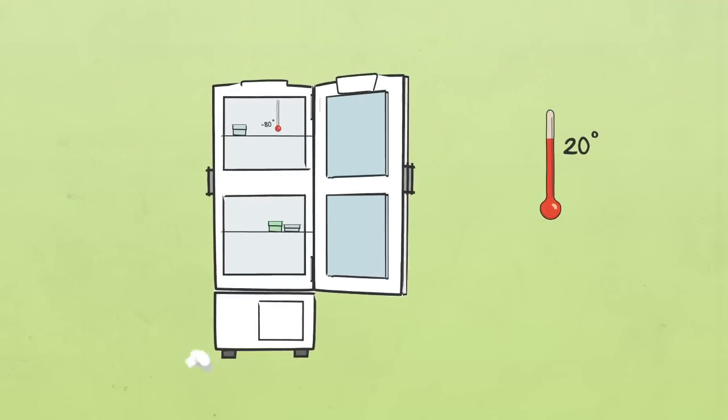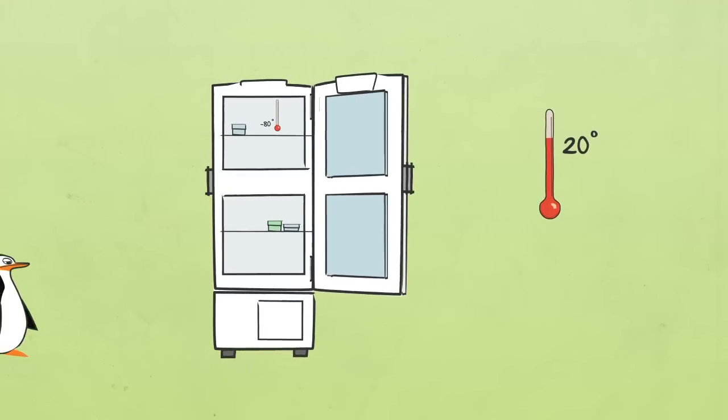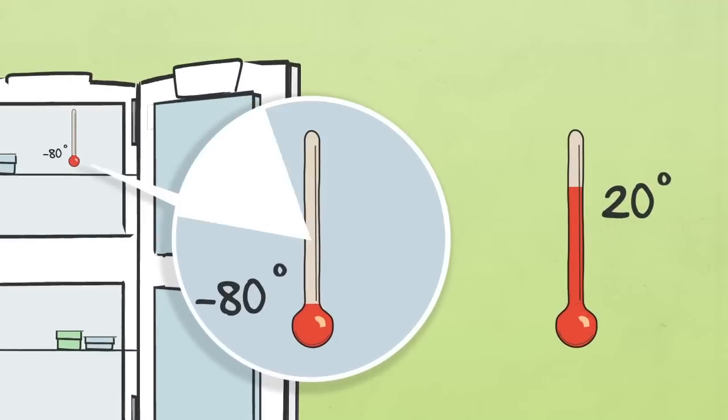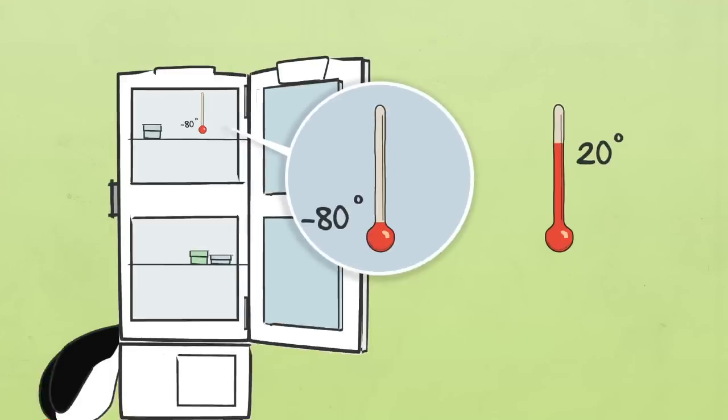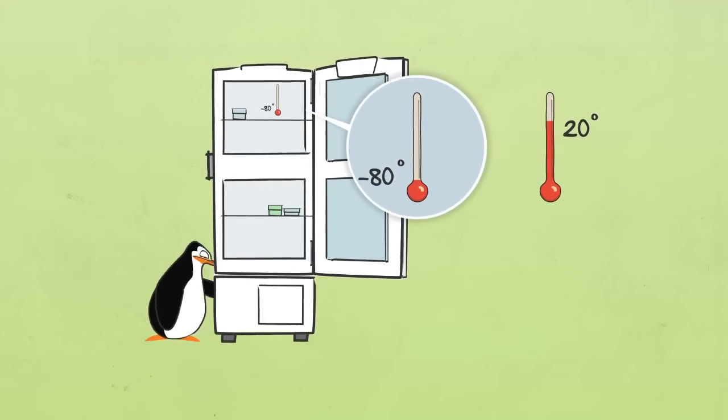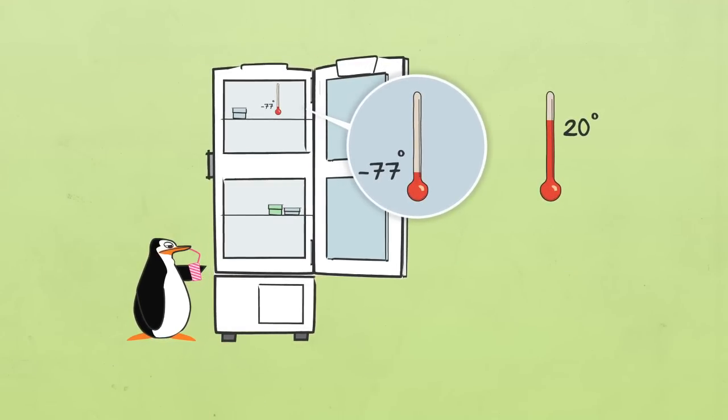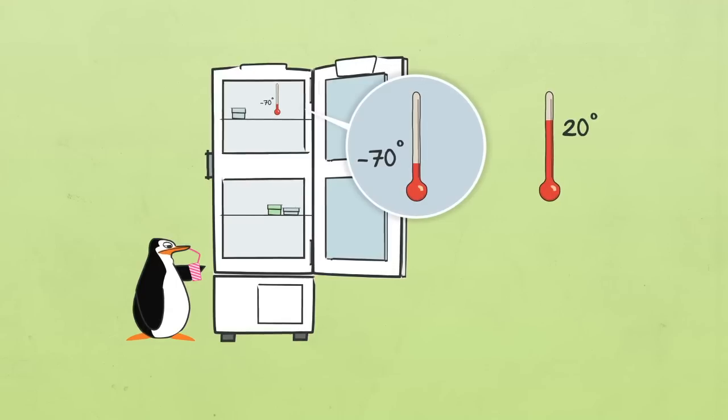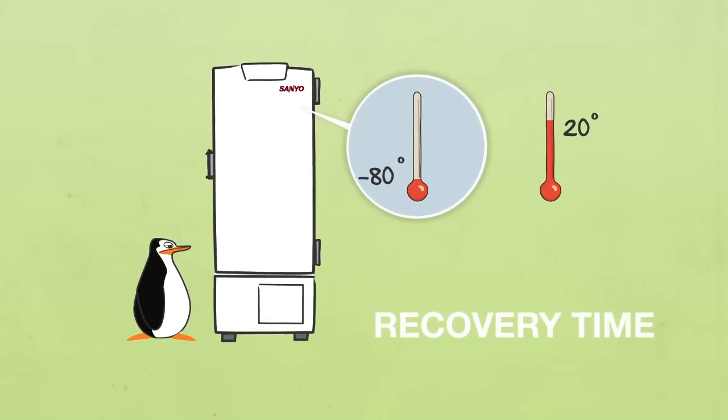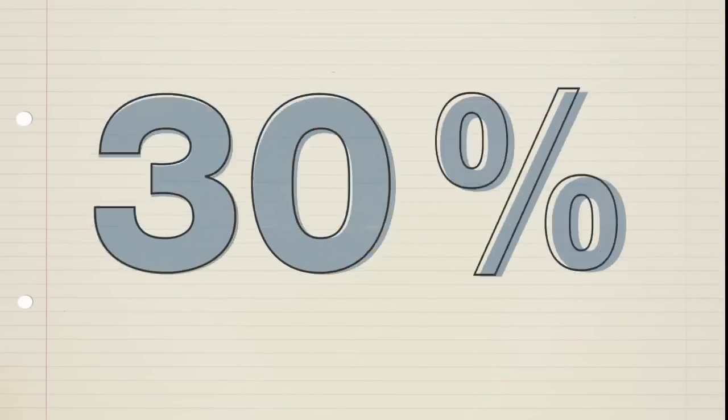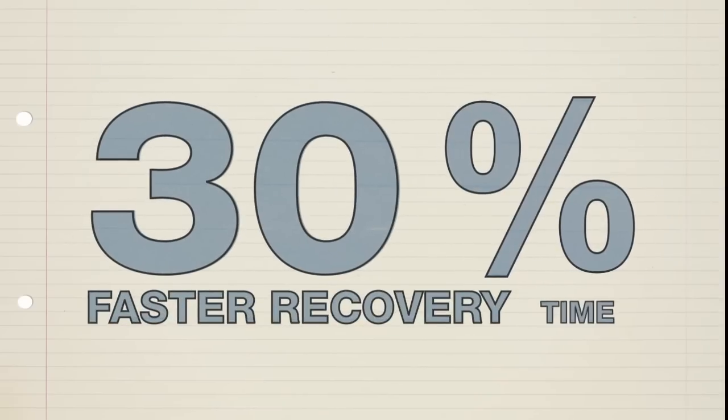Another advantage. If you open the door of a freezer, the difference in temperature in a freezer compared to its surroundings is easily 100 degrees Celsius. This means that the freezer temperature rises immediately. And for samples, it's important that after closing the door, the freezer temperature drops quickly. This is called recovery time. A water-cooled freezer has a 30% faster recovery time compared to an air-cooled freezer.